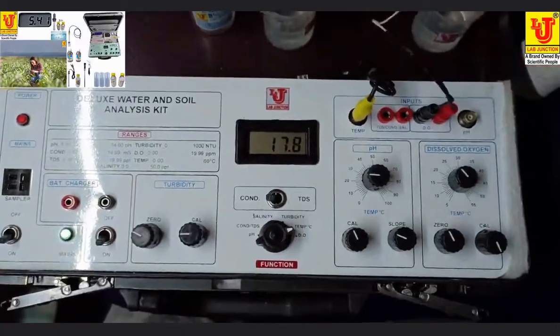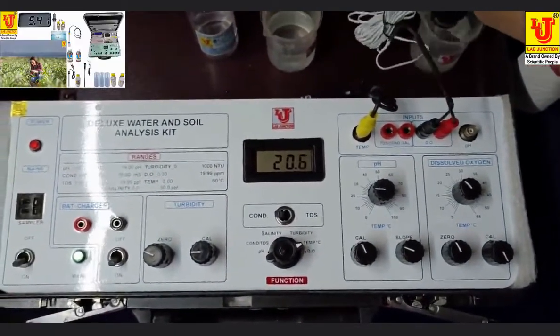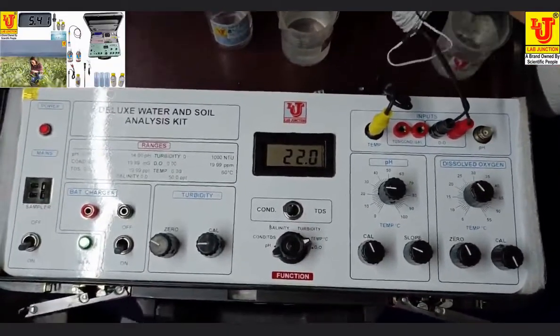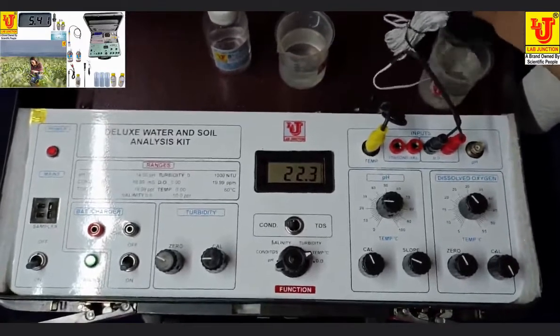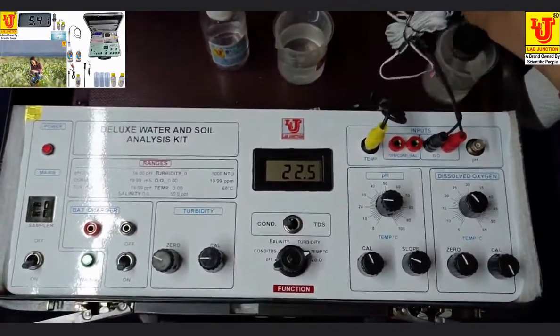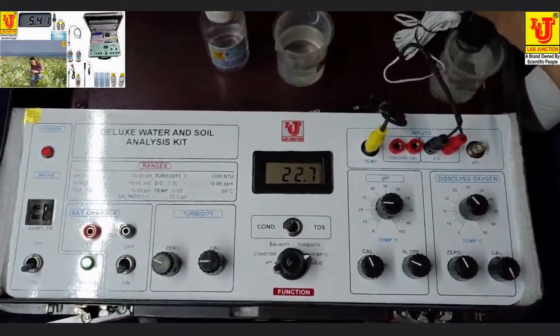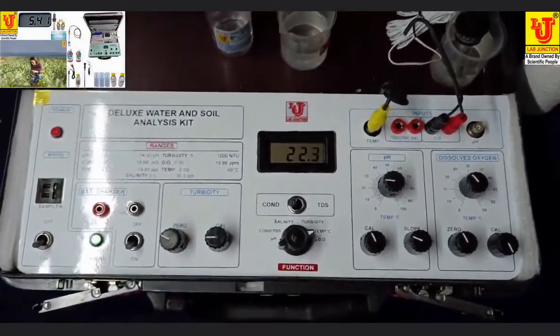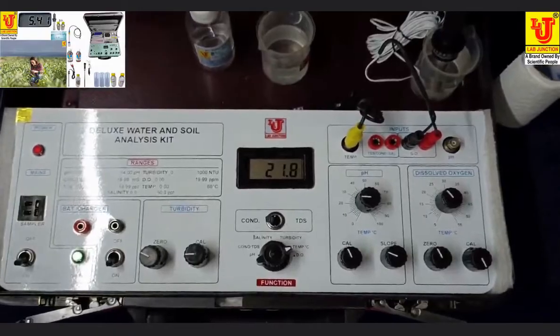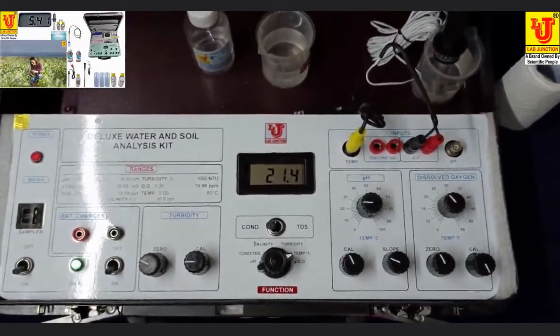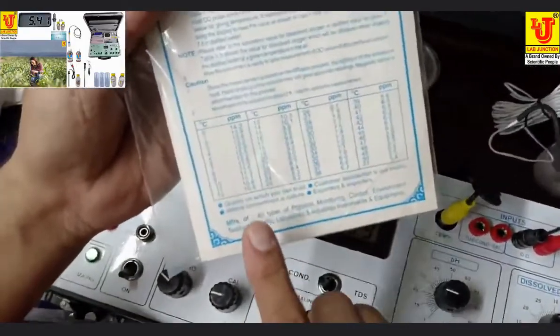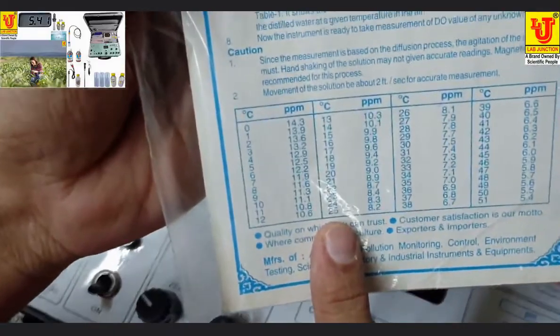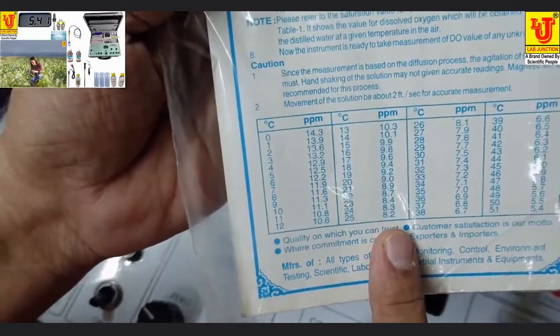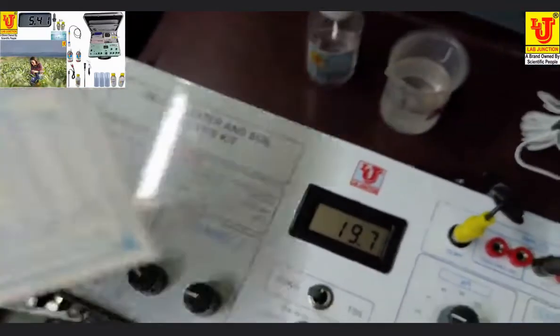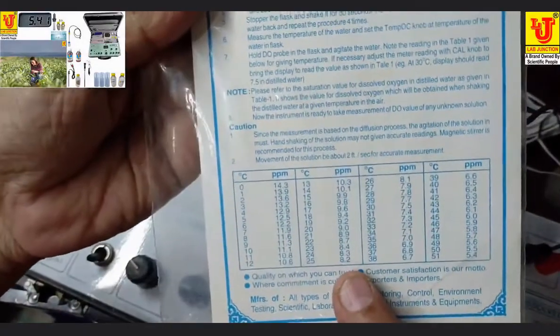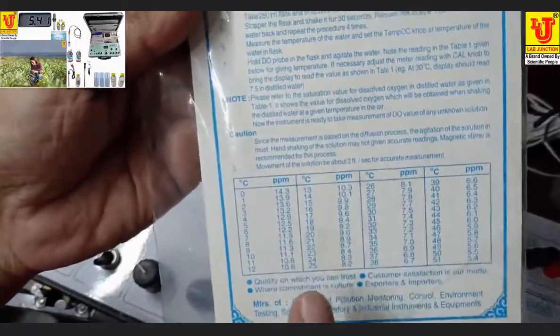Now dip your DO probe cum sensor in distilled water and feed the saturation value of dissolved oxygen as per the table. Like this, at 25 degrees, the saturation value is 8.2 ppm. You can set this 8.2 ppm like this.